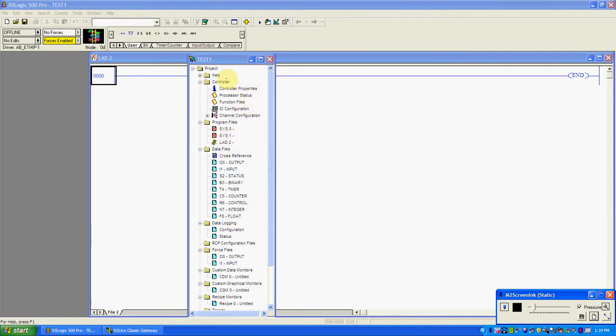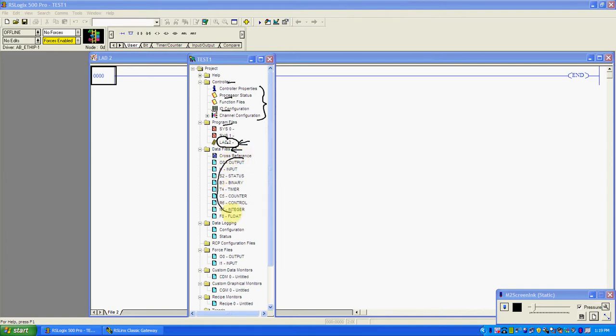In the controller tab are all your controller properties. This includes stuff like processor type, communications type, channel config, setting up of the inputs and outputs, processor faults, and so on. Next is program files — this is where all of your ladder logic and program logic exists. The logic always starts with 2 and ends with 2, so they give you this one as default and we'll add more in a later lab. Data files are simply where we store the information we're going to work with, and data files are referenced in the ladder logic.